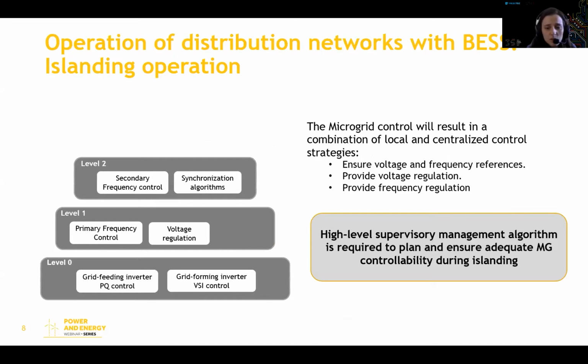However, this autonomous operation can be quite challenging, where we require specific voltage and frequency regulation strategies that are usually provided only by conventional generation. So in this case, for these small islands, we need to consider advanced control strategies of the distributed energy resources to provide voltage and frequency regulation. So based on the microgrid concept, we can adopt this multi-level control architecture that combines local and centralized control strategies.